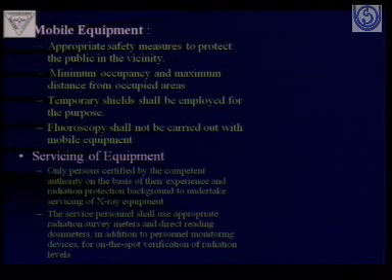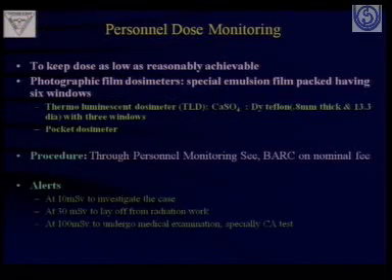For the mobile equipment also, there is a requirement of safety in terms of a screen. Especially a screen has to be there. And for fluoroscopy, of course, it has to be meticulously planned and stringent requirements should be followed. Servicing of equipment has to be done by competent personnel, that is, an engineer registered with the AERB. Again, there is a requirement of AERB clearance in terms of engineers also.